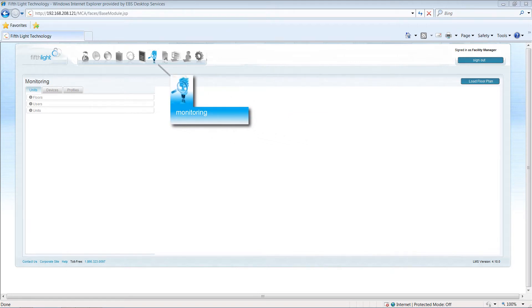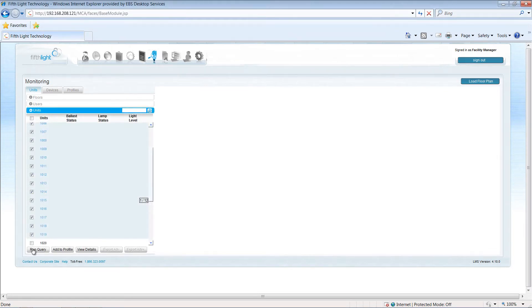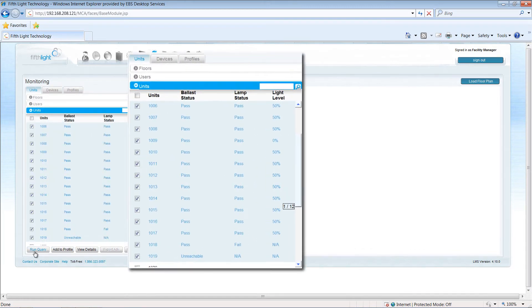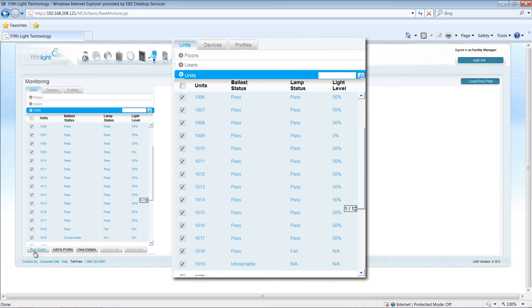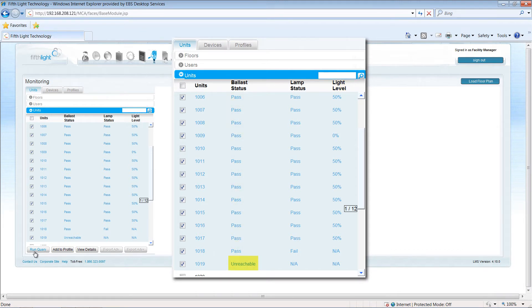The monitoring module allows facilities managers to query selected devices for current status. The status information shows the current light level as well as whether the device is online or offline. Fluorescent fixtures will also indicate whether lamps are burnt out.